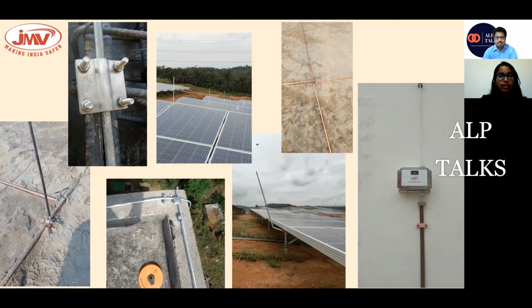This is the parapet conductor and the holders, because we need to lay the conductor along the complete parapet wall. Then we need to interconnect it with the air terminal. There also, at every 1 meter, I need to connect the holders and the connectors. On buildings we don't need to insulate it, right? We can directly touch the building, right? We use bare conductors.